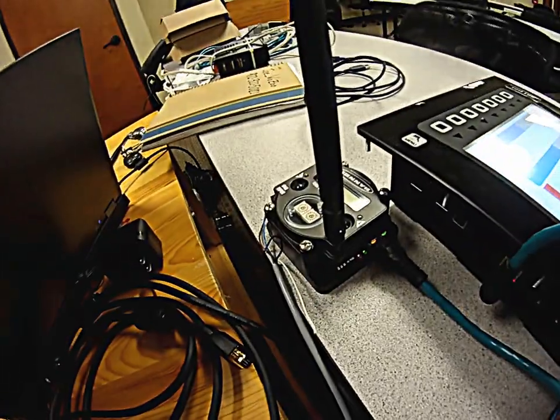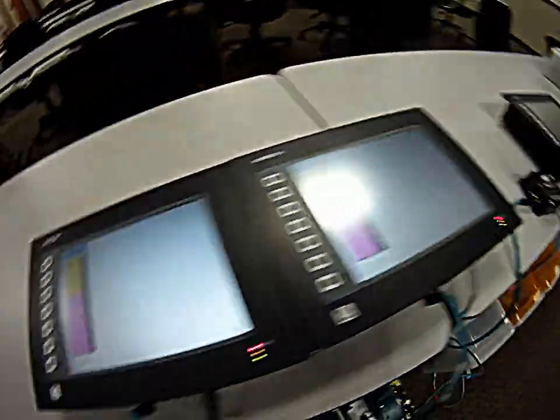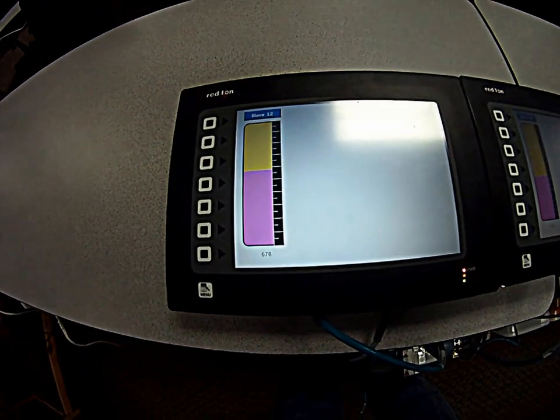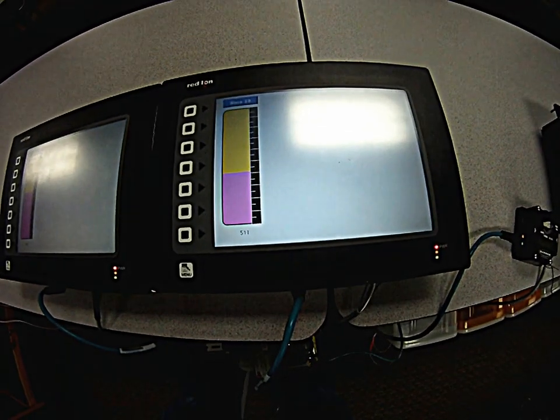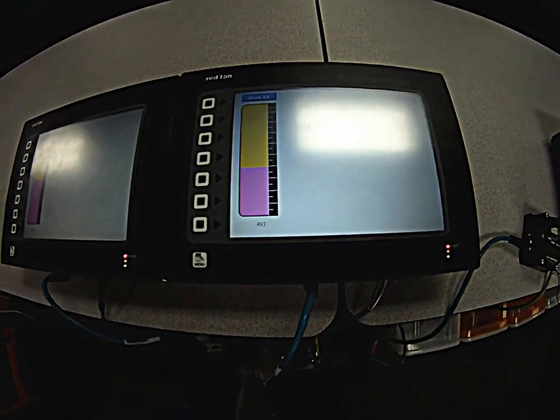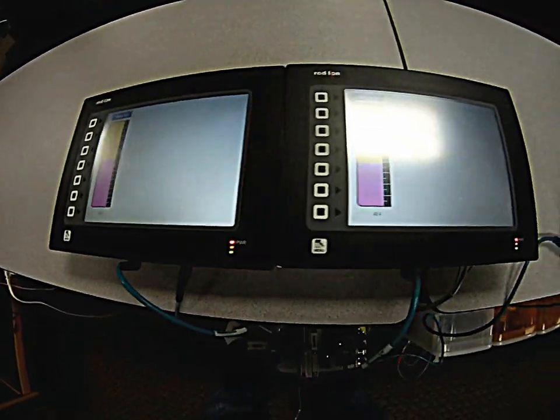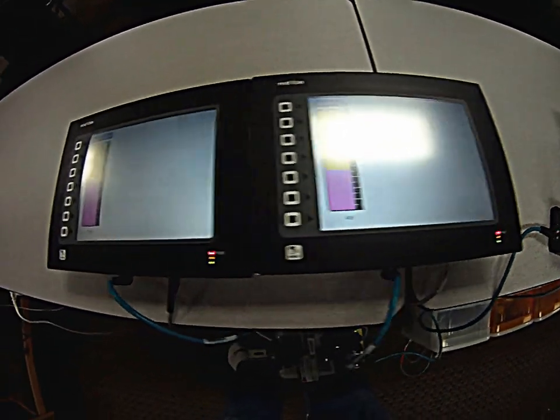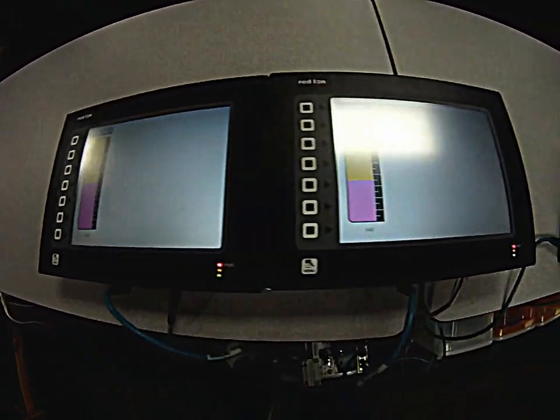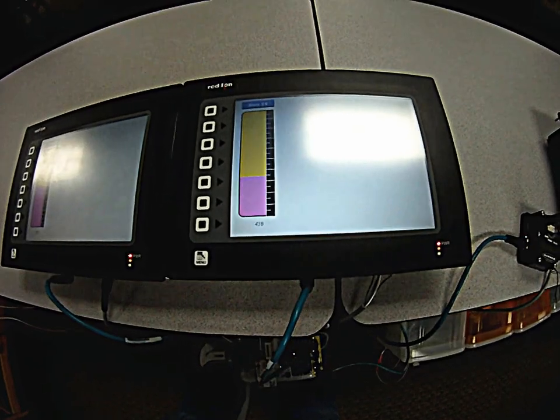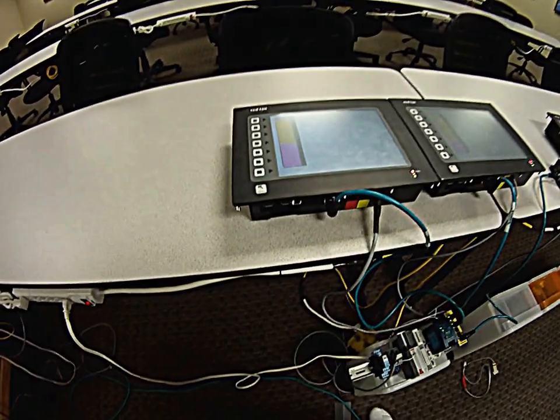So if we go ahead and turn on both these guys on the wireless connection, we're cranking right through that Banner radio right there. And you can come over here and you can see there's that Banner radio there. And you can see this guy is working away. And this guy is working away. So there is a little bit of delay, but it does get caught up. Certainly not used for, say, streaming video, but you can get the concept here with Modbus TCP communications happening. Thanks.